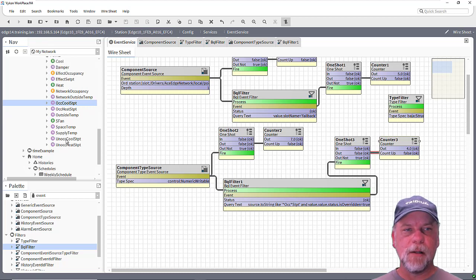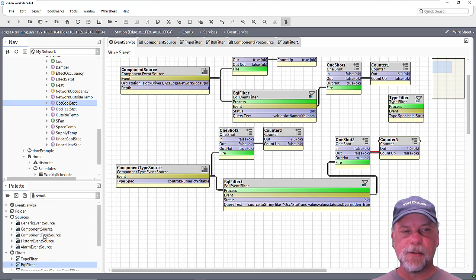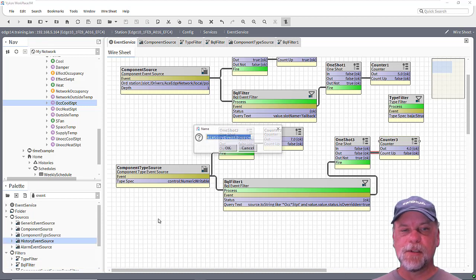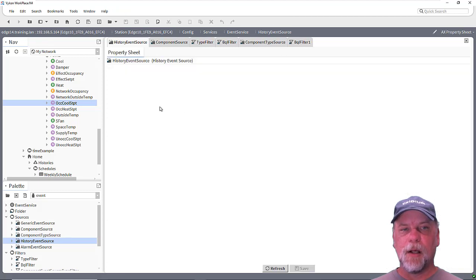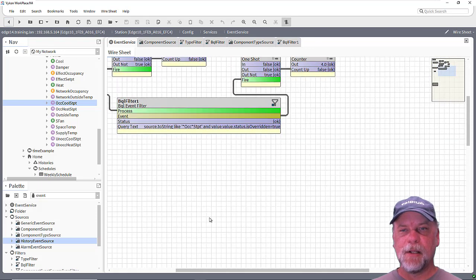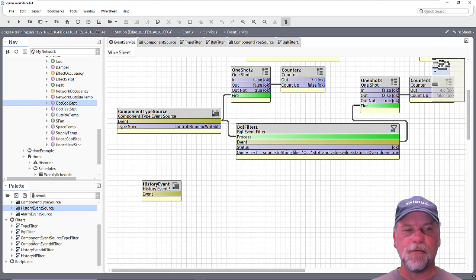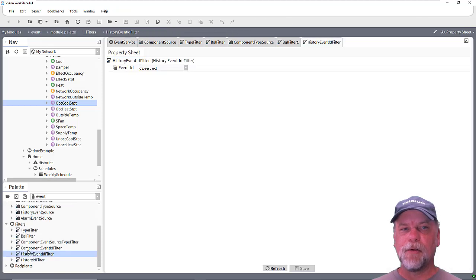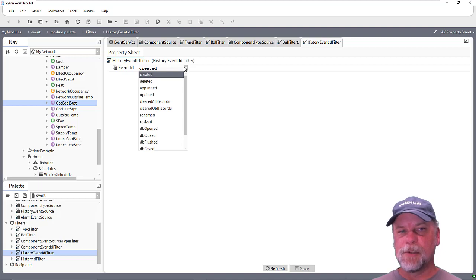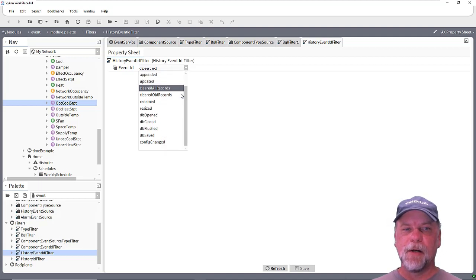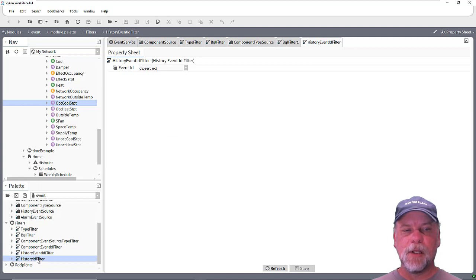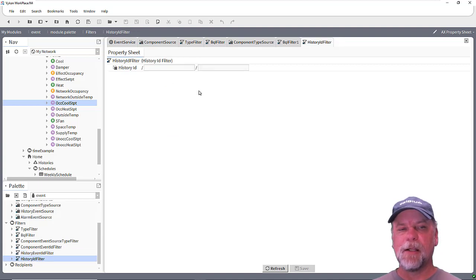Now there are other things we could do with the filters or the sources. We could monitor for certain history event sources. When you look at a history event source, there are no configuration properties — it's just monitoring for all history events in the station at that point. But when you look at the filters, there's a history event ID filter, so you could narrow it down to only specific types of history events that you're interested in. There's also a history ID filter where you can specify the history ID and that would narrow down to specific items as well.